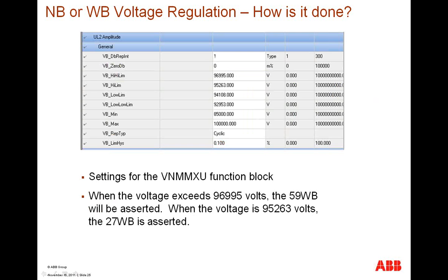So voltage regulation, how is it done? Here are the settings associated with the VNMMXU function block. This function block is a phase to ground function block. For instance, I have a setting here set for the high limit. This high limit is associated to the 59 wideband mode.